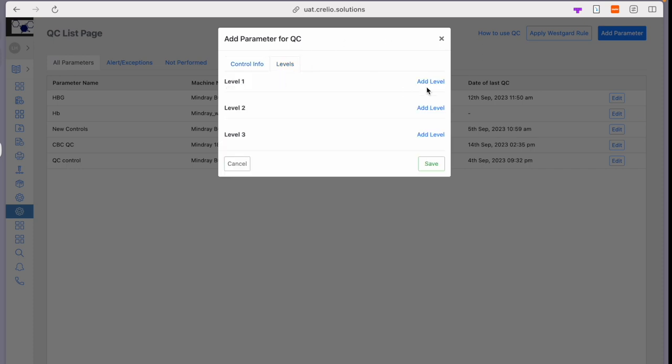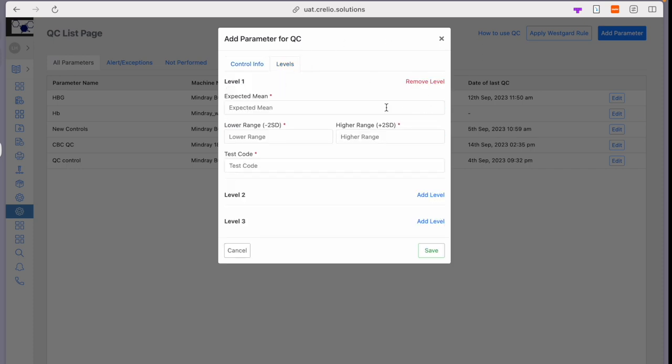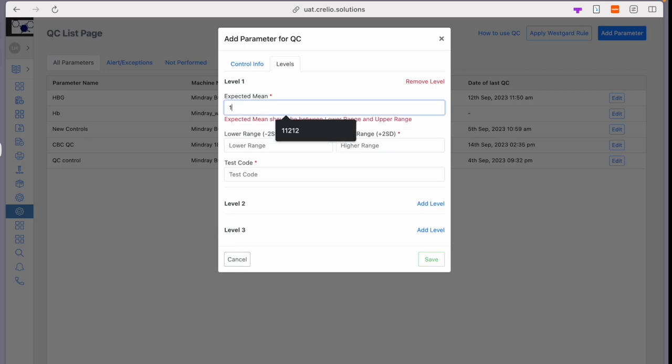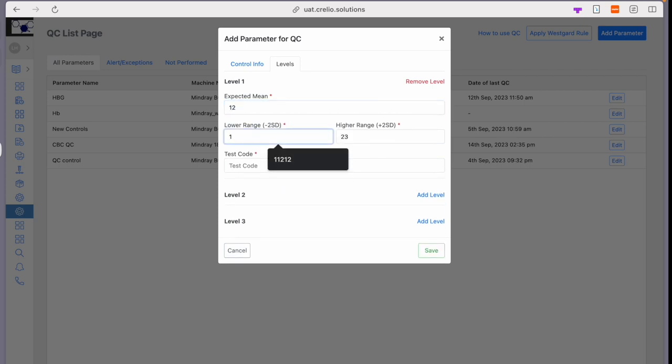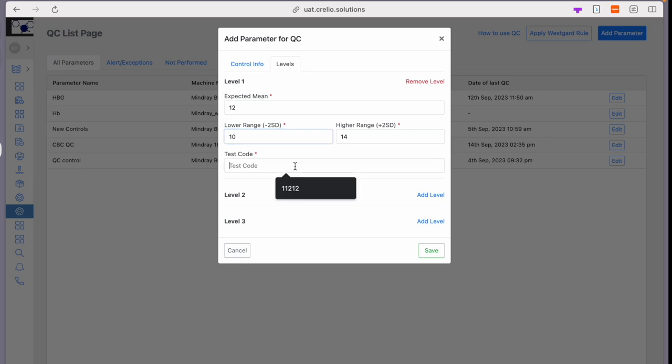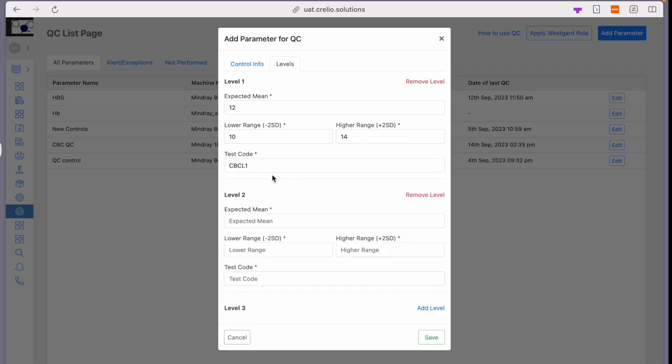Then select levels. In the level, you need to enter the expected mean as per defined by the manufacturer and the test code. This test code is used for interfacing.